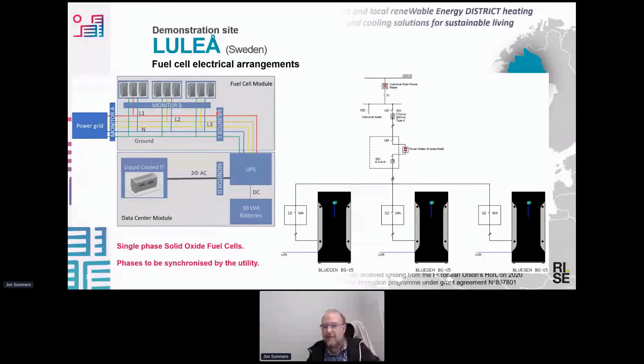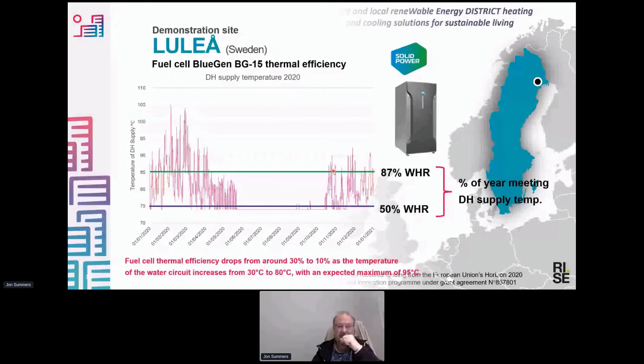In terms of last year's temperature, what was the temperature of the district heating network? It's a 3rd generation network, so we can probably reach 95 centigrade, meaning we could reject into the district heating network at about 90 degrees, covering 87% of the year. The other 13% we won't be able to match the temperature, so we would let the systems reject heat through the chimney stack involved with the fuel cells.